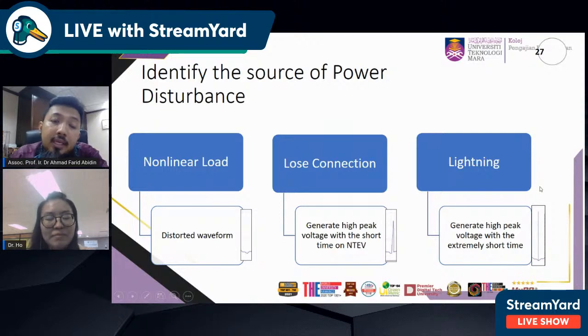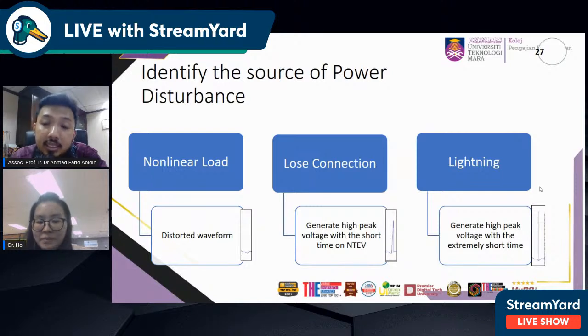So if a high neutral to ground issue appears in our system, we can suspect it's coming from the non-linear load, it can be coming from the loose connection, or it's coming from the lightning. Lightning is an external factor, whereas non-linear load and loose connection are internal factors. So it's much easier for us to pinpoint the problem that has been faced in the system, which is related to the high neutral to ground voltage or high neutral to earth voltage.